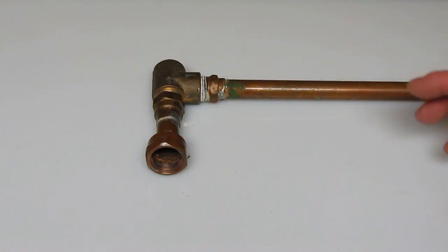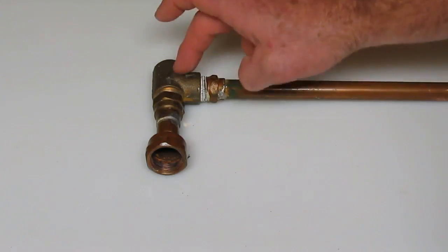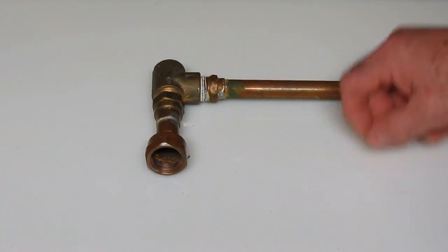These valves are all there for a safety reason. So they should be piped six inches down off the floor. Never plug or reduce a relief valve.